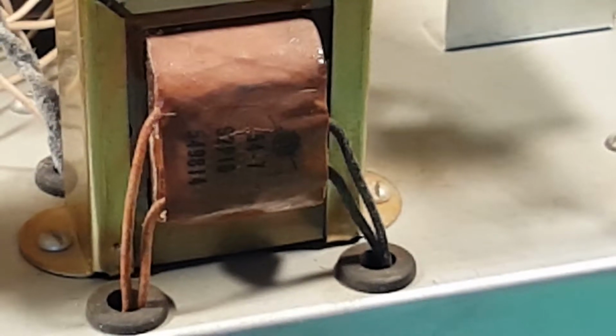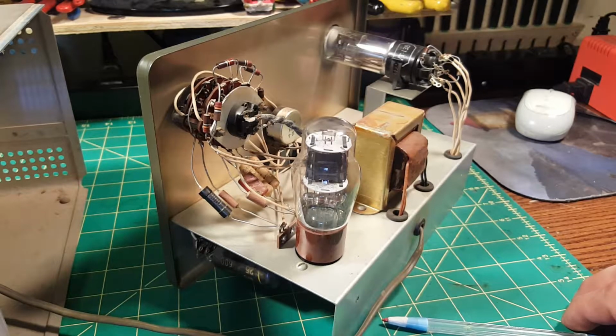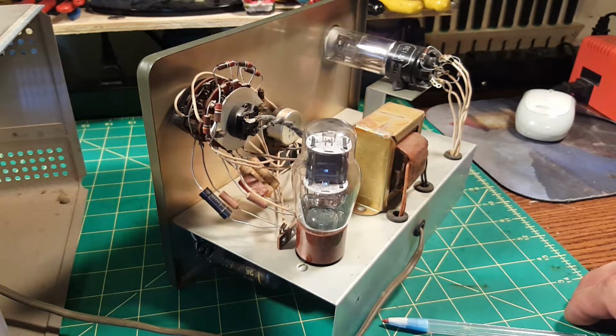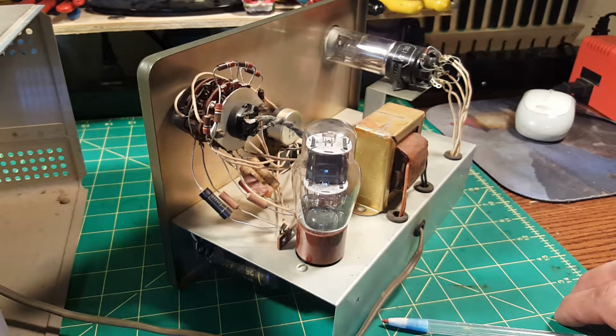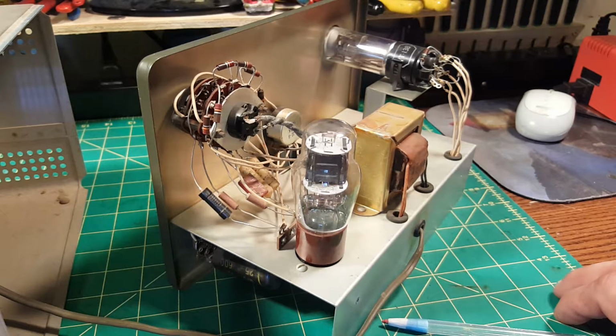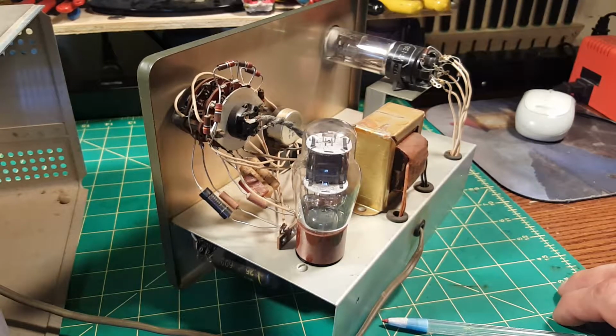I take an overall look at the top side of the unit, at the components - how many of them have been replaced is what I'm interested in. I'll also look at the vacuum tubes: are they the OEM manufacturer, are they the right ones? That gives an indication of how many hours of service are on this unit.